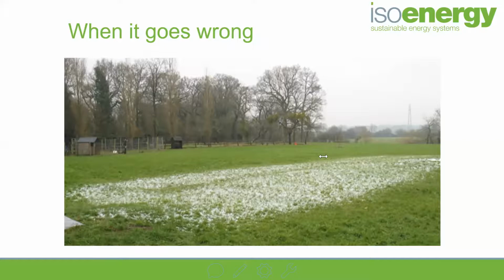Chris, do you look to reverse heat pumps to recharge the ground or rely on the solar input? You should rely on the solar input. As I say, when you're looking at cooling and dumping heat into the ground, you can't rely on that because you might have a very mild summer where it's not that hot and you don't need that much cooling. So if you're relying on putting 20% or 30% of the energy back into the ground and you don't actually do that because you're not cooling with the system, then you're going to be in a bit of a sticky wicket for the coming winter where your ground temperature starts off lower.